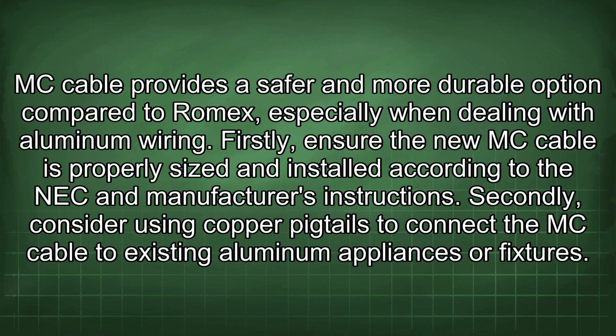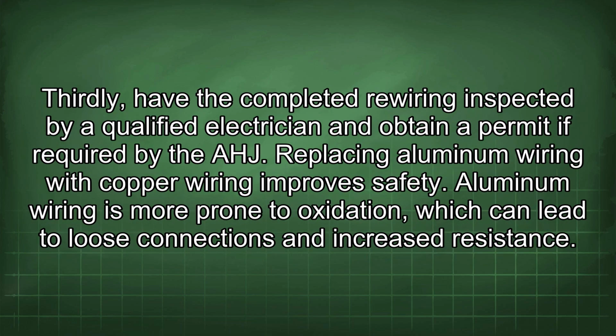Firstly, ensure the new MC cable is properly sized and installed according to the NEC and manufacturer's instructions. Secondly, consider using copper pigtails to connect the MC cable to existing aluminum appliances or fixtures. Thirdly, have the completed rewiring inspected by a qualified electrician and obtain a permit if required by the AHJ.